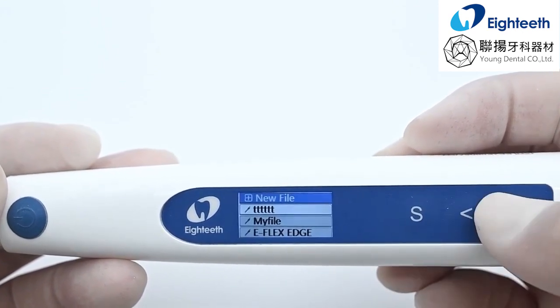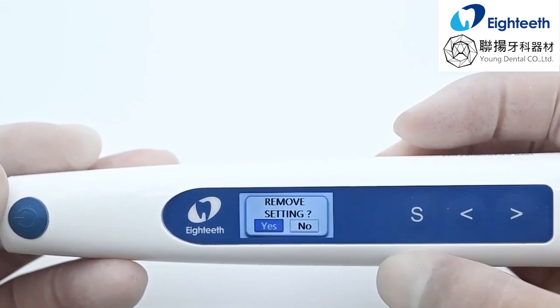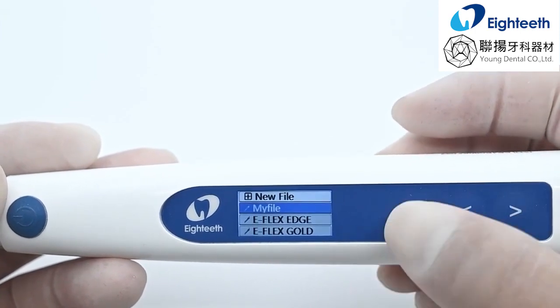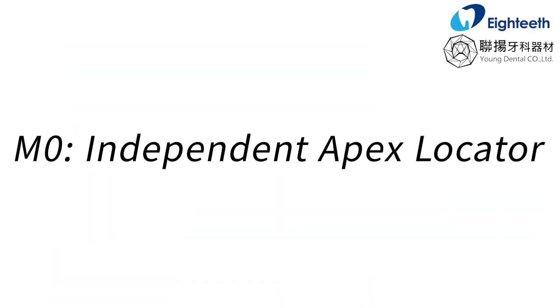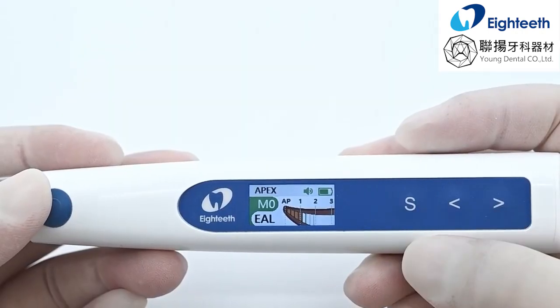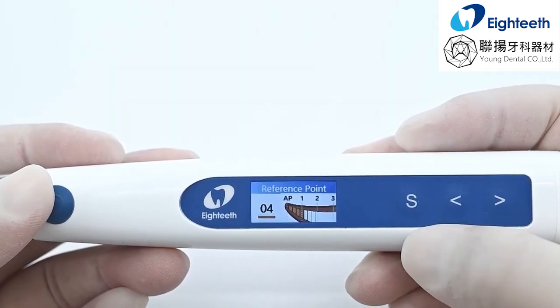If you want to delete the newly created mode, select the mode and long press the setting button to delete. M0 is a separate mode for root canal measurement.